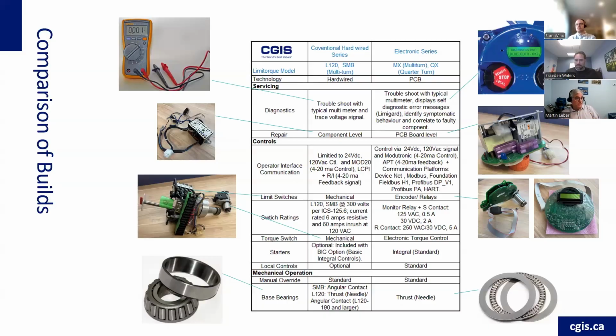That's the electronic series. Now, uniquely, look at the switch ratings of the hardwired series, the L120 and the SMB, and compare the ratings for the electronic series. These actuators, the hardware, were developed in a different era when electronics wasn't as prevalent. So back then they ran higher current loads through the switches to start a motor or give a signal to start up a pump, or whatever the actuator did.